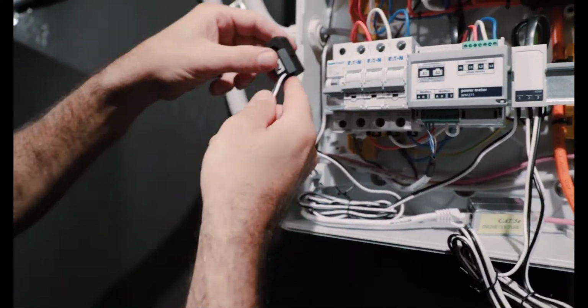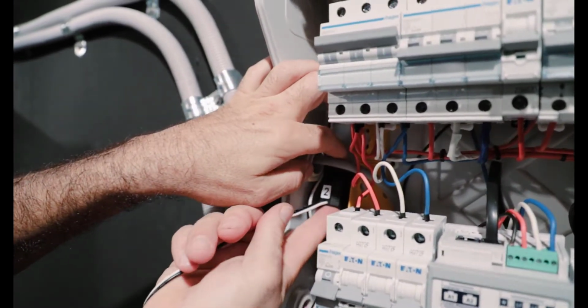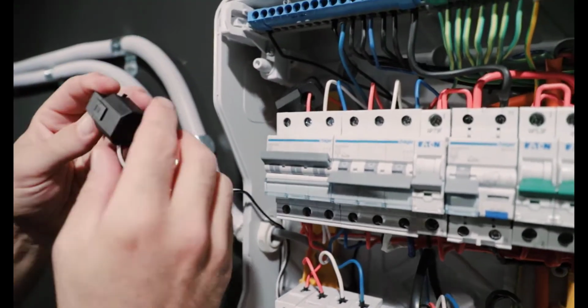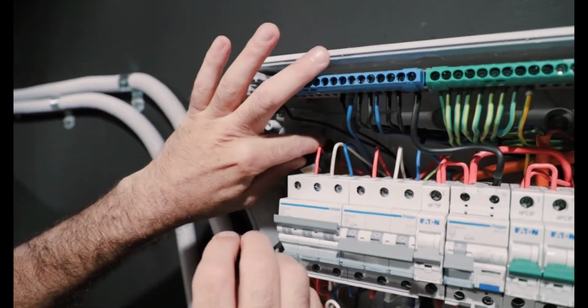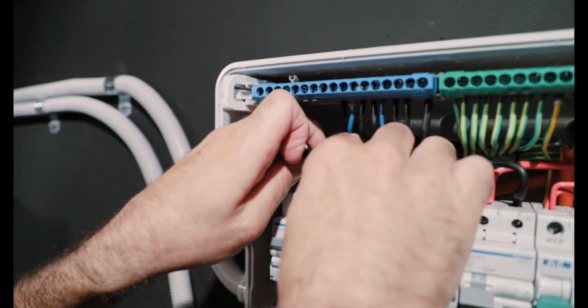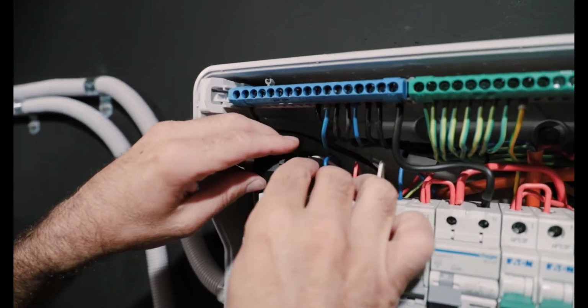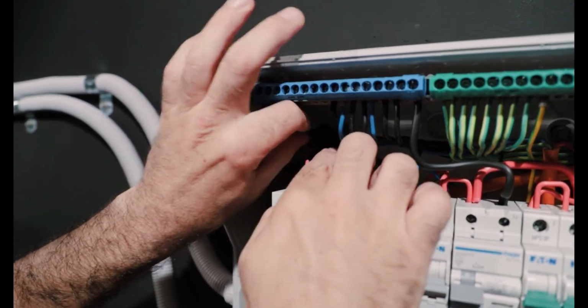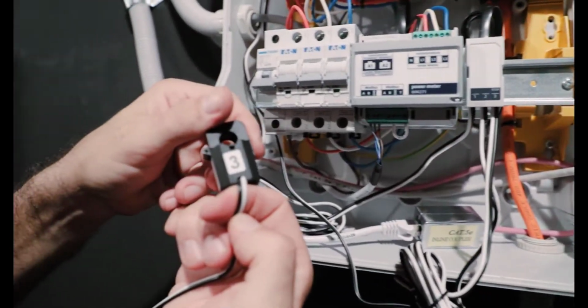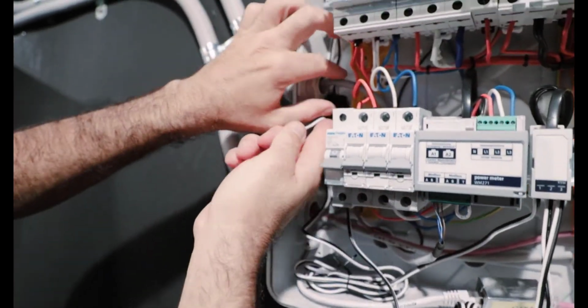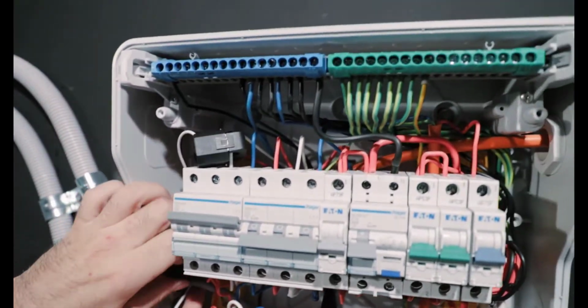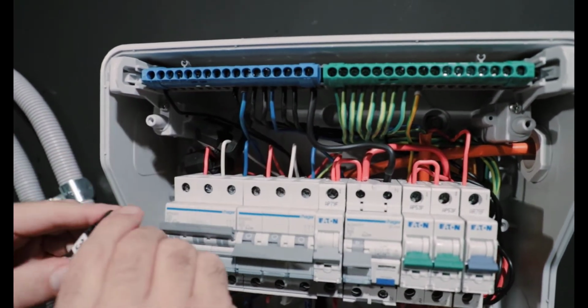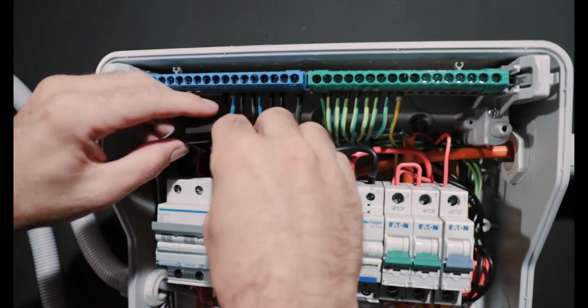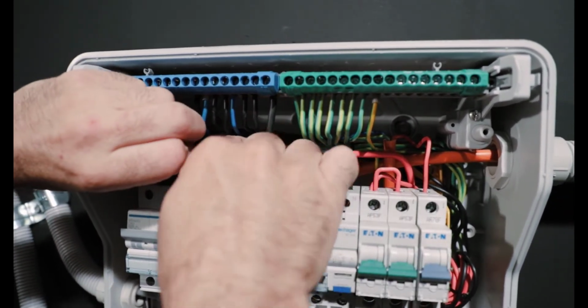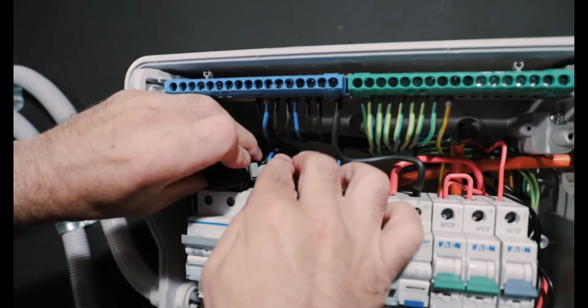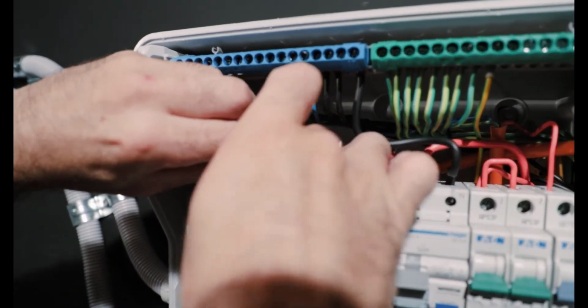It is important to make sure we get the CTs on the right phases. That's why they are so clearly labelled 1, 2 and 3. If you don't, it can be identified, hence the reason why we need the 3 separate isolators, but unfortunately there's nothing we can do on the back end to reprogram it. It will be a case of having to revisit the site and put the CTs onto the correct phases if they have inadvertently been connected onto the wrong phase.